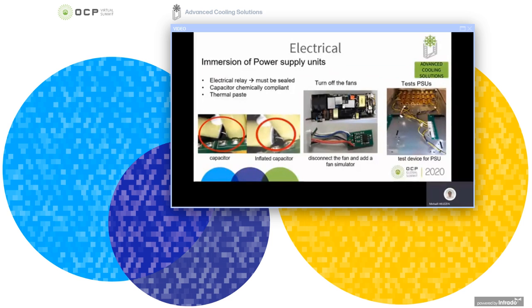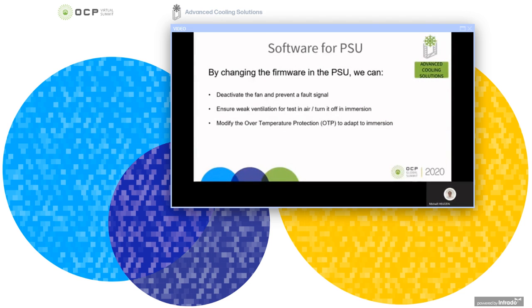Once all these points are perfectly under control, we test this power supply with a test bench specifically made for immersion. You can see it in the picture on the right. I shared with you the physical tests we can do for the power supply units. It's also possible to make changes directly in the firmware of the power supplies. It can be done upstream by the manufacturer, and you can deactivate the fan and prevent the fault signal, ensure weak ventilation for tests in air, turn it off in immersion, and modify the over temperature protection to adapt to immersion if necessary. It depends on the constraints of the project.